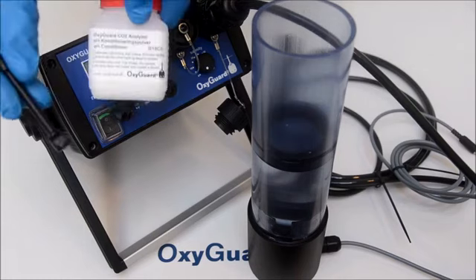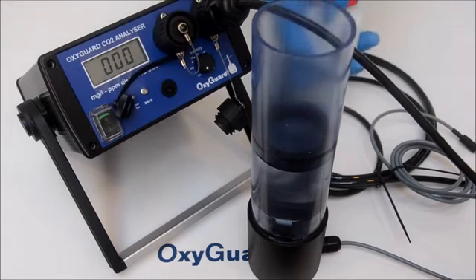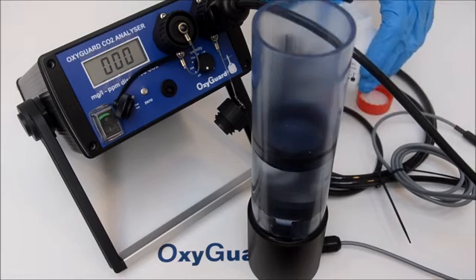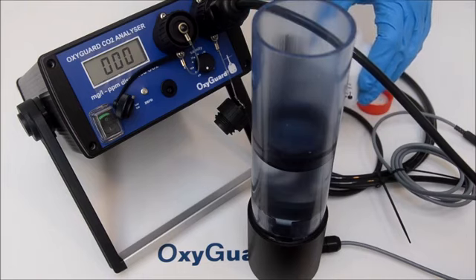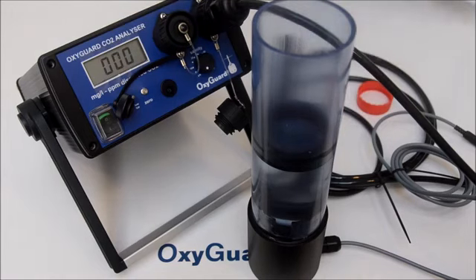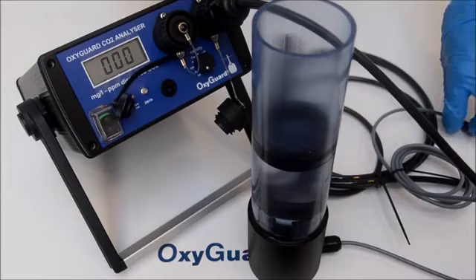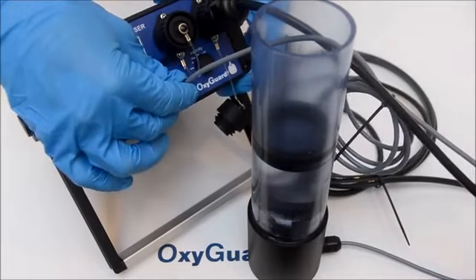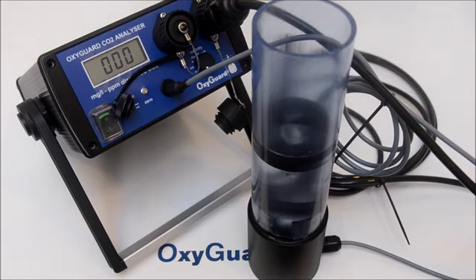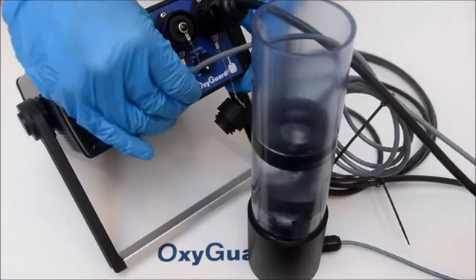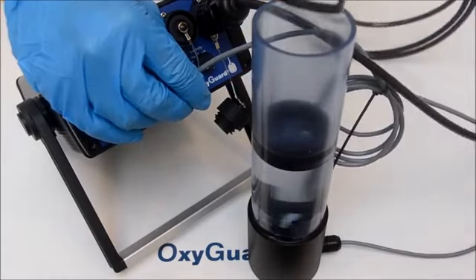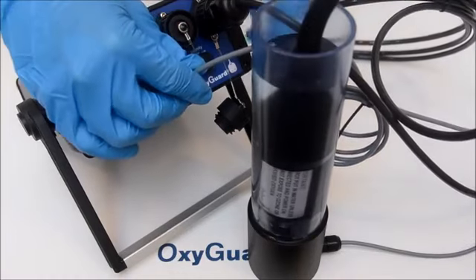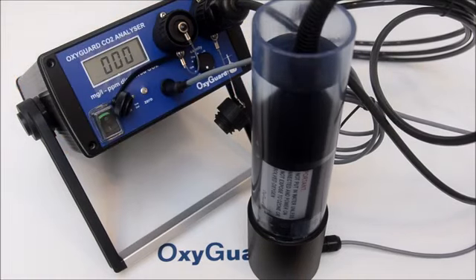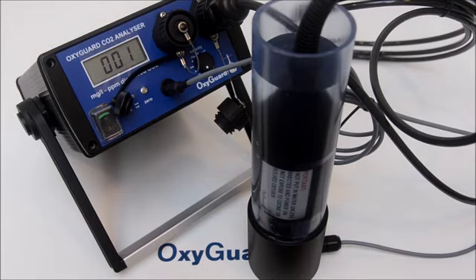Add 1 measuring spoon of pH conditioner. Stir until powder has dissolved. Stop the stirrer, place the probe in the beaker, and start the stirrer again. When the reading is stable after about 5 minutes, check the reading. If it's less than 20 mg per liter, the water is approved for use.